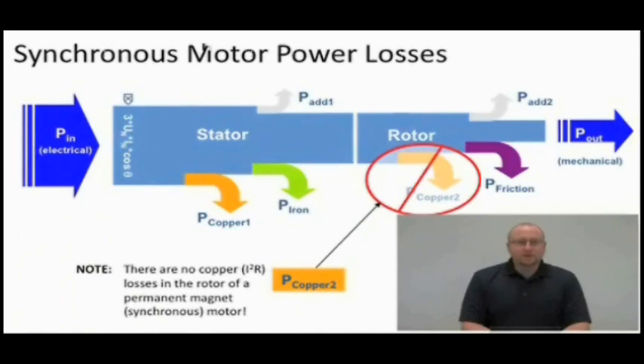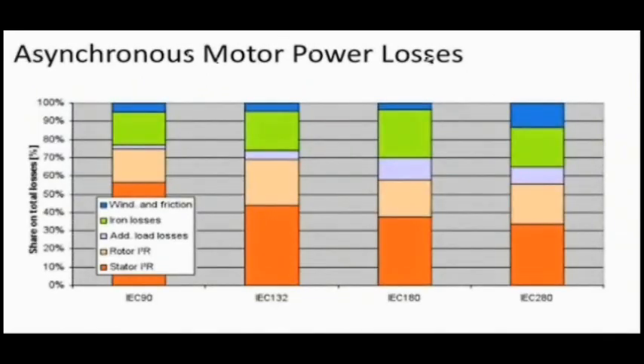Interestingly enough, in a synchronous motor, that means a motor that has permanent magnets on the rotor and there is no slip, there are no copper losses in the rotor, so inherently a synchronous motor is more efficient than an asynchronous motor. But for today's discussion, we're going to talk about asynchronous motors since they are by far used more often and they're less expensive than a synchronous motor, so there's just more of them out there. It could make a larger impact in our conservation of energy by attacking asynchronous motors. If we look at the relative losses in an asynchronous motor, the majority of the losses are copper losses. If you look at those two big orange bars at the bottom, those are your losses in the stator and your losses in the rotor due to copper losses.